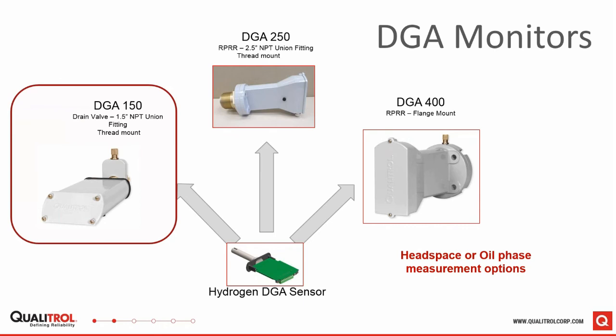The distinctive feature of the DGA150 is that it's IP68, so it's fully submersible. And that's a feature that, from speaking to people within the industry, can affect up to 50% of all transformers in certain utilities. So there will be 50% of transformers that will be at least at some risk of flooding at some point in time. And DGA gives you submersible measurement of hydrogen. In addition, DGA150 can operate in either the oil phase or in the headspace of the transformer. So it has flexibility to be configured to measure gas in oil or gas in headspace.